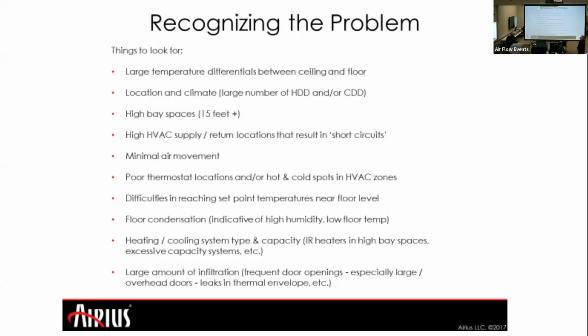Okay, so recognizing the problem: when you walk into a location, you ask, is it going to work in this space where I'm at? So things to look for: large temperature differentials between the ceiling and floor, location and climate, high bay spaces, high HVAC supply and return locations, the short circuiting that you might run into, minimal air movement, which is huge. I remember when I first got into HVAC, they said the most important thing to learn was airflow. The second thing was airflow. So it's just air circulation. It was just huge.